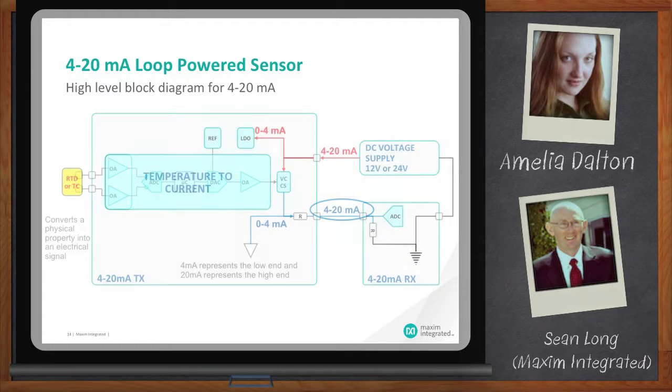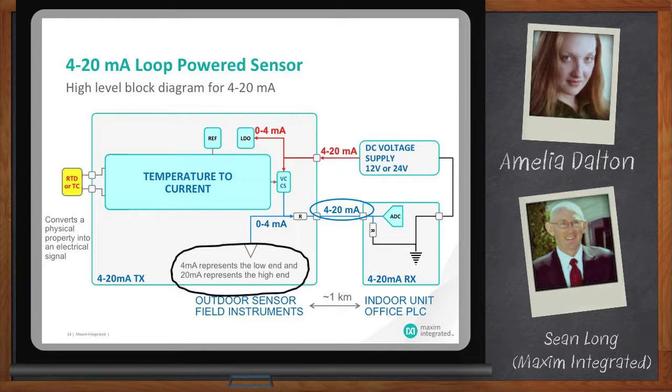Okay. You're going to have a 420 milliamp transmitter card. Now, that's going to take the sensor input, either maybe an RTD or a thermocouple, convert that physical property to the electrical signal and essentially do a temperature to current conversion. Gotcha. Okay. It's going to connect to the 420 milliamp loop. In this case, 4 milliamps would represent the low end. For example, if you're measuring between 200 degrees C and 800 degrees C, 4 milliamps would represent 200. Yeah. And 20 milliamp represents 800.